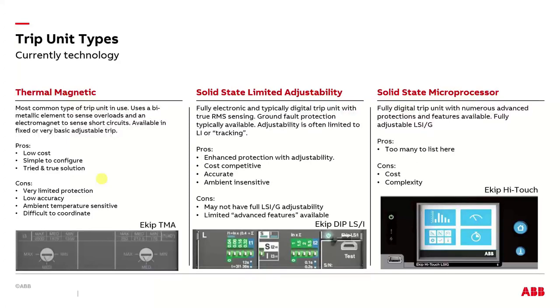The cons, they offer very limited protection. They're good for cables and some small transformers, and they provide, you know, adequate protection for that. So they're kind of a code minimum solution, but that's going to apply to a lot of your jobs, commercial, even industrial. So they're the ubiquitous breaker out there. They're low accuracy, and they're low accuracy essentially due to the thermal element, because, and we go to the next one, they're sensitive to the ambient temperature. So if you have a hot ambient, that breaker will tend to trip early. If you're cold, the breaker is going to trip long, and that's on the order of seconds or tens of seconds. So it's a big wide gap.